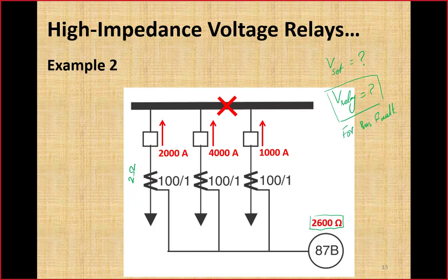So here we proceed by first developing its equivalent circuit, so that we have a full understanding of what is going to happen in case of a close-in external fault and a bus fault. Let me draw the circuit over here. For the first circuit, this is its magnetization branch in series with the resistance of the series branch, which we assume to be 2 ohm. That is the first CT. In circuit 1, I have omitted the ideal current source here, so I will assign that current to the branch.